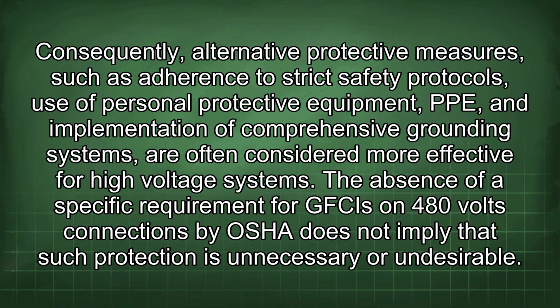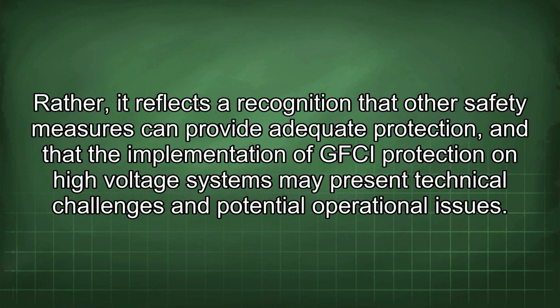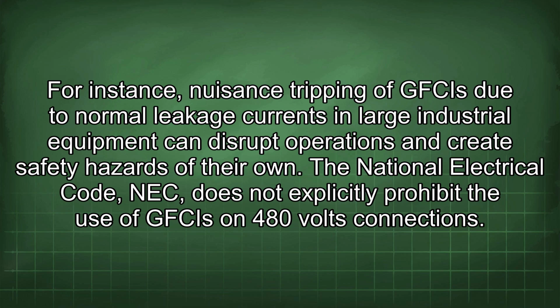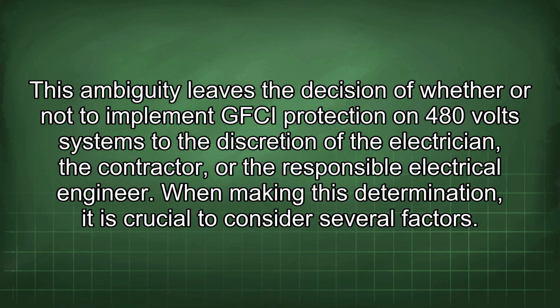The absence of a specific requirement for GFCIs on 480 volt connections by OSHA does not imply that such protection is unnecessary or undesirable. Rather, it reflects a recognition that other safety measures can provide adequate protection, and that the implementation of GFCI protection on high-voltage systems may present technical challenges and potential operational issues. For instance, nuisance tripping of GFCIs due to normal leakage currents in large industrial equipment can disrupt operations and create safety hazards of their own. The National Electrical Code, NEC, does not explicitly prohibit the use of GFCIs on 480 volt connections. This ambiguity leaves the decision of whether or not to implement GFCI protection on 480 volt systems to the discretion of the electrician, the contractor, or the responsible electrical engineer.